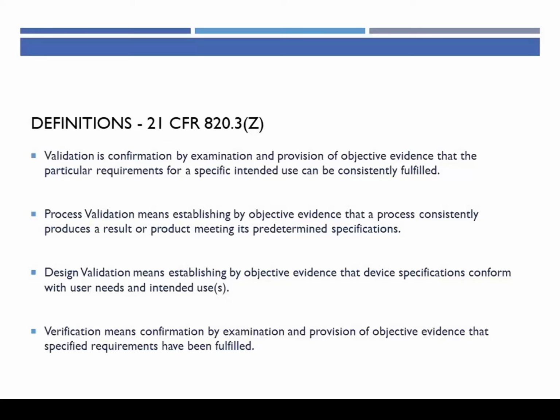Now, design validation is different. Here we see that it means establishing by objective evidence. Okay, we know what that means. But here it changes. The device specifications conform with user needs and intended uses. So this is saying the products you make are safe and effective for your users. You meet their needs. So process validation shows that the process can make acceptable product. Design validation takes that product and shows that it meets user needs and intended uses.